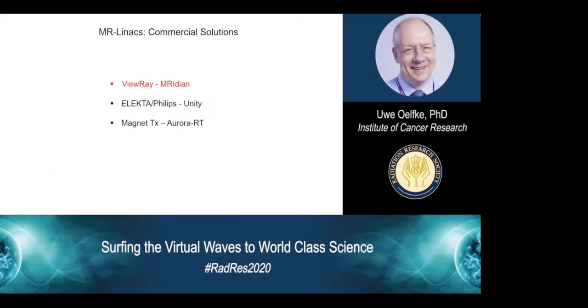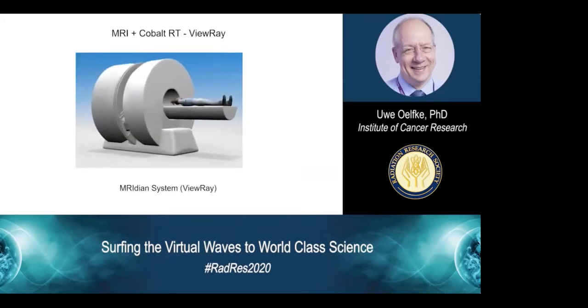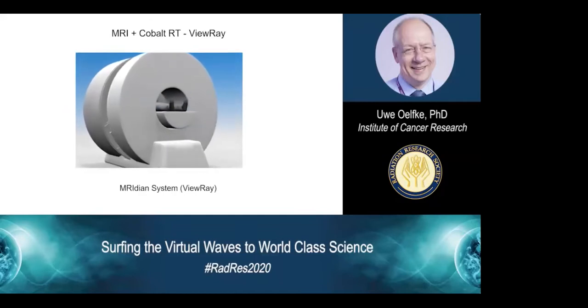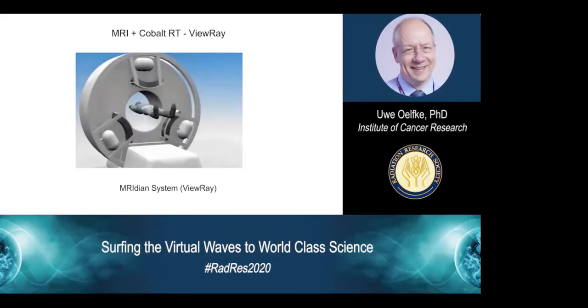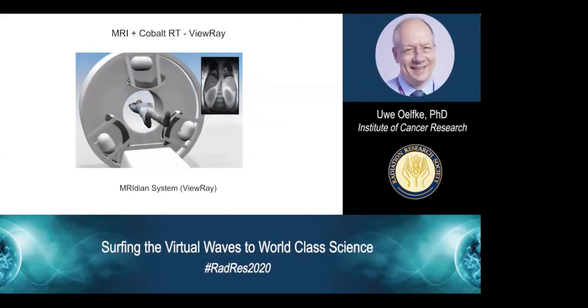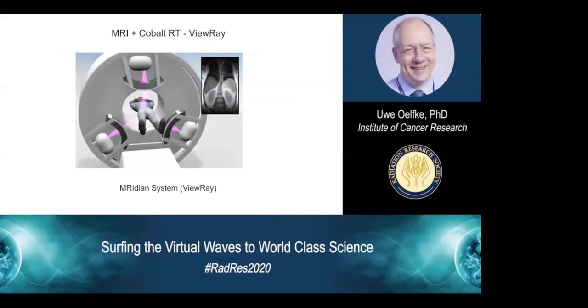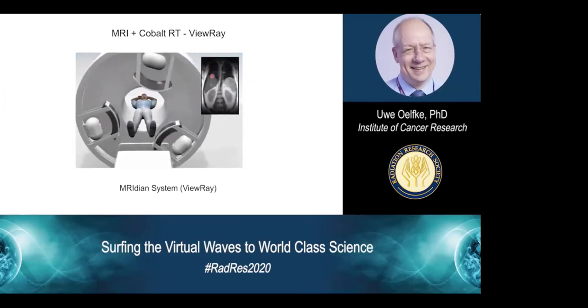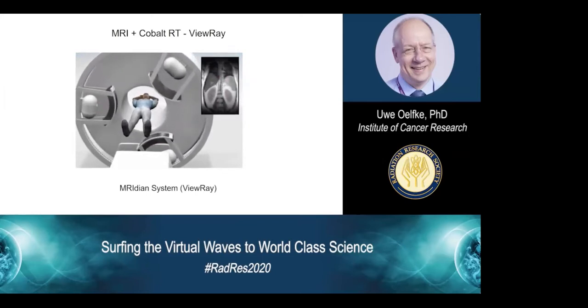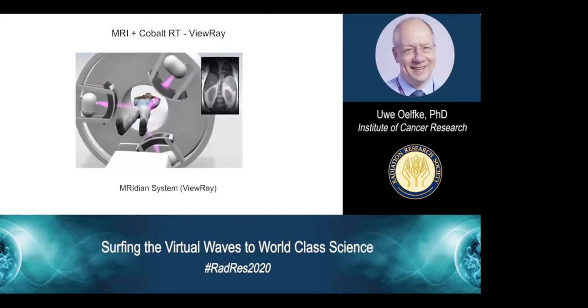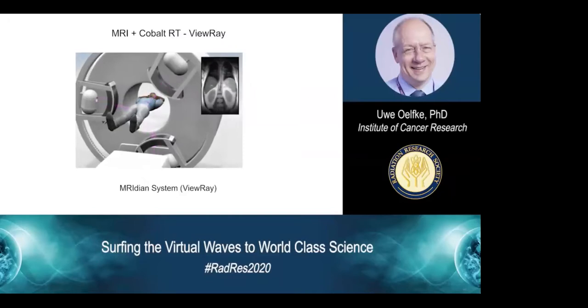Let's start with the commercial solution of ViewRay, the MRIdian system. This was actually the first pioneering system, and it went into clinical operation already in 2014. You see here an animation of how it works. So the patient goes into a split magnet, and you have actually 3 cobalt sources which can be used simultaneously. So you have 3 multi-leaf collimators, and while you're observing the patient anatomy, you can use this information to adapt your radiation field to the observed patient anatomy.